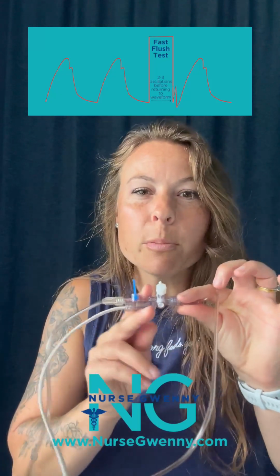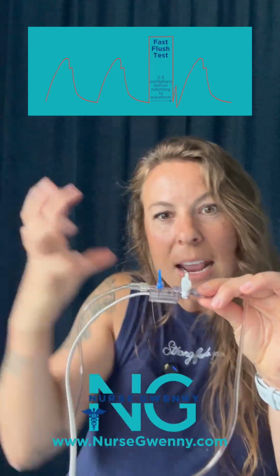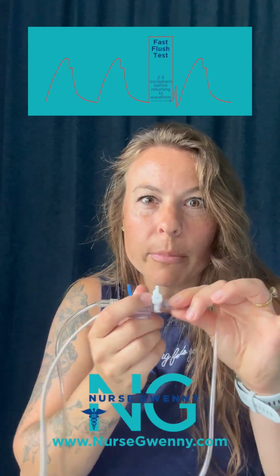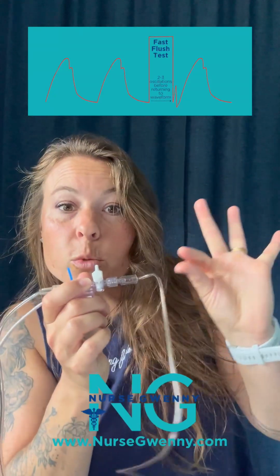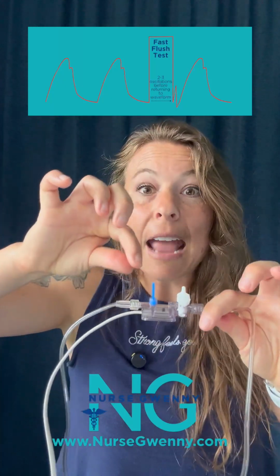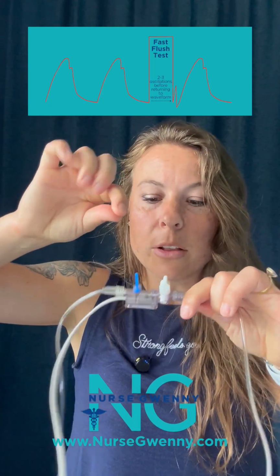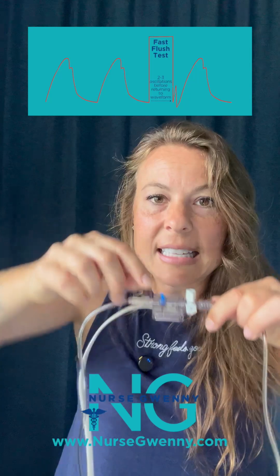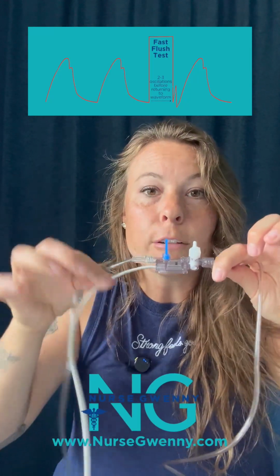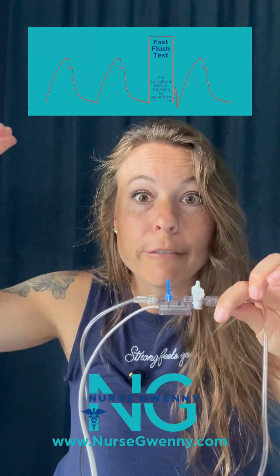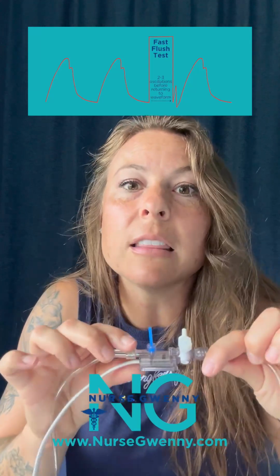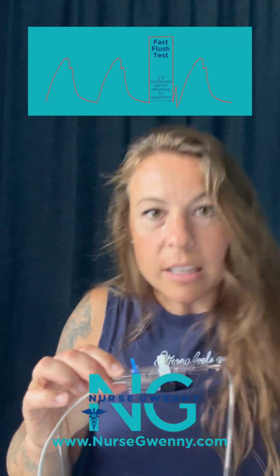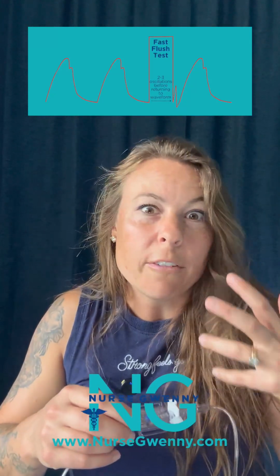That's just a reference point for the transducer to be able to compare, okay, we know that this side is 300 millimeters of mercury, and it compares what it's hearing from the patient, and that allows it to spit out that reading. But every once in a while, when you pull this pigtail, or there are some brands where you squeeze the cassette, it opens up the floodgates from that 300 millimeters of mercury fluid bag and gives it a little fast flush to help clear the line of any bubbles, or if you've got a little bitty clot there on the end of your catheter.